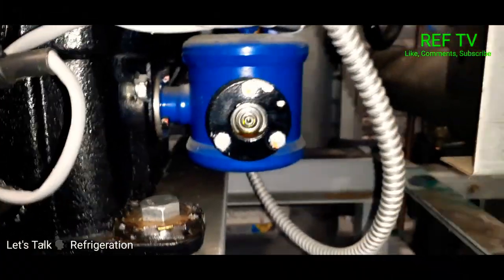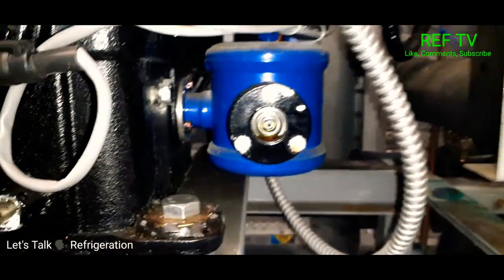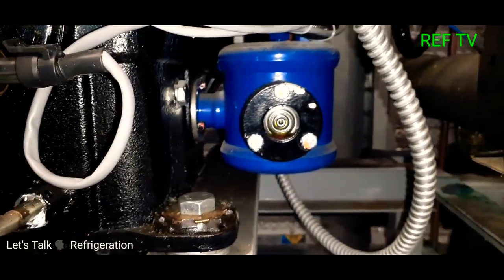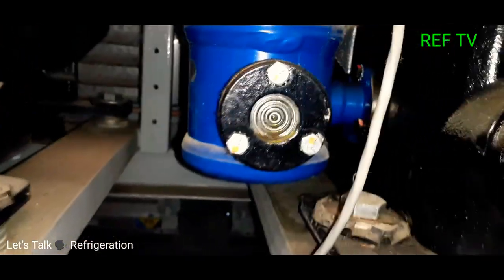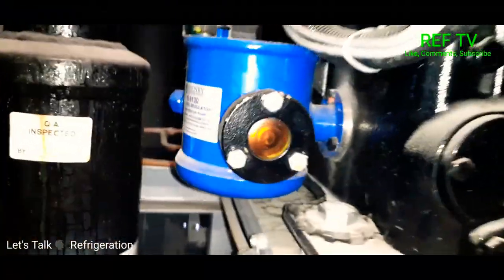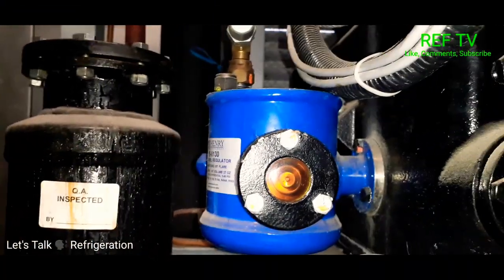All right, so I'm checking my oil pump for compressor number 3. And as you can see, we have no oil at all. Let's just check compressor 2. Compressor 2 was running. It didn't trip out. But as you can see, we have no oil. Here's compressor 1, look at that. Just full of oil. So, got some oil issues here. And basically running a high suction pressure due to that compressor being tripped off on oil.